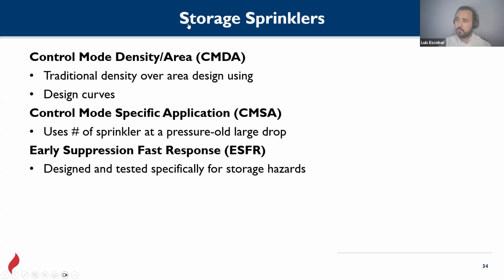Control mode density area for storage sprinklers, control mode specific application, and early suppression fast response. These two are pretty similar. I would say these two are the most common for retail stores or for specific use, for example tire storage or roll paper storage. Remember, we're talking about storage in this slide. And the most common, and I would say easiest, way to protect a storage system would be with the ESFR sprinklers, designed and tested specifically for storage hazards.